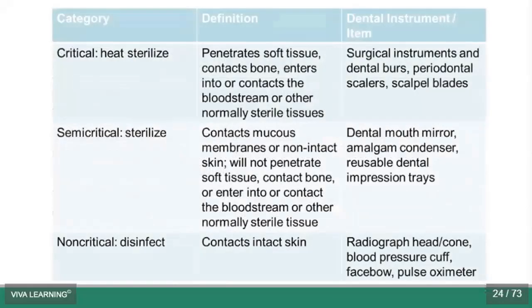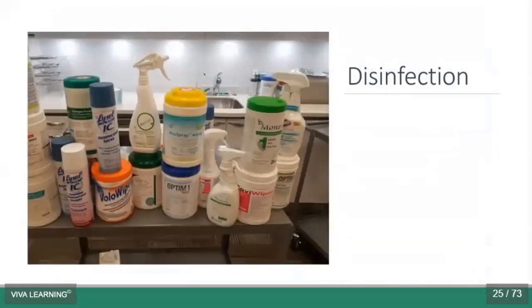And ideally, heat sterilization, right? And always following the manufacturer's IFU, or instructions for use. So we want to make sure we're following the IFU. Non-critical items include radiograph heads and cones, blood pressure cuffs, face bows, pulse ox. Everything else we expect to be single-use disposable or heat tolerant, or at a minimum being able to withstand high-level disinfection if the IFU specifically states that. Ideally, we would want those items sterilized.